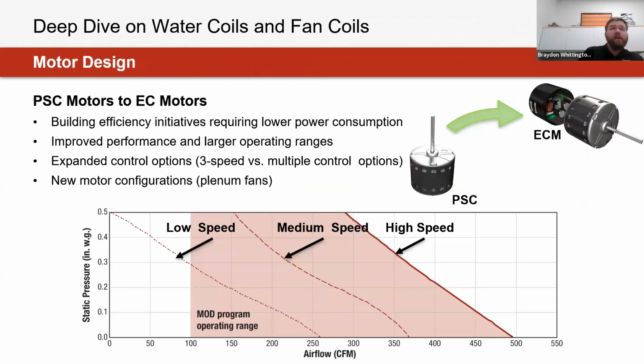So we mentioned that all of these come with a fan. Well, what type of fans are these commonly provided with? For a lot of those retrofit systems, or ones that you would see in the past, a lot of these were paired with PSC motors, or permanent split capacitor motors. But what we're starting to see, not only when we're talking about water coils with higher temperatures for our chillers or lower temperatures for our boilers, but also from an energy perspective, is a lot of fan coil manufacturers shifting to utilizing EC motors with this equipment as well.